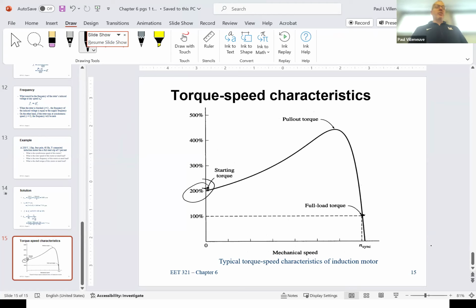And if I'm running this much torque, what happens? Well, I'm pulling more current through the machine than it's rated, and it's not spinning, so you don't have the cooling effect of the fan, the blade that's on the rotor shaft that's pulling air through the machine. So the winding tends to get heated up, and if you don't stop it, it will catch on fire.